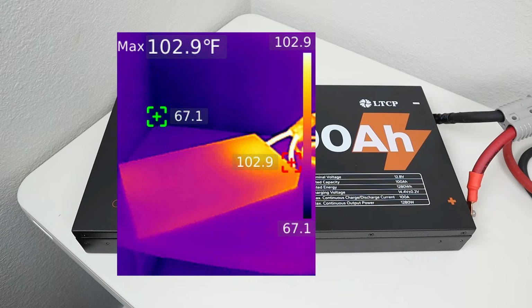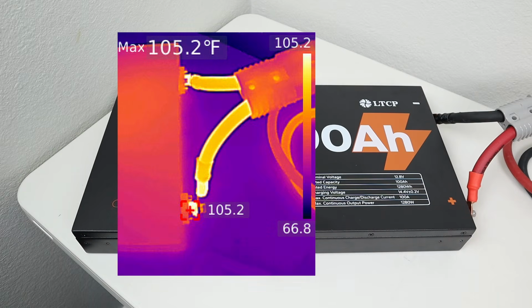If we look at the thermal images of the battery, you can see the battery is actually pretty cool. The warmest part was the positive conductor at 102.9 degrees Fahrenheit, and zooming in on that a little bit more, the positive terminal was at 105.2 degrees. So under max load, that's not too bad. It'll be interesting to see what conductors they use on the inside.